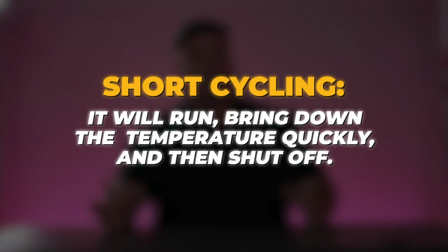An oversized system is just as bad. It will do something we call short cycling, meaning it will bring the temperature down quickly because it's oversized, and then shut off. Wasn't that great? No, because one of the things your air conditioning system does is remove humidity from the air. An air conditioning and heating system doesn't just heat and cool the air, it creates comfort. In the cooling season, they create comfort by removing humidity from the air. If it's short cycling, you're not going to get that humidity out of the air, and it's not good for your system.